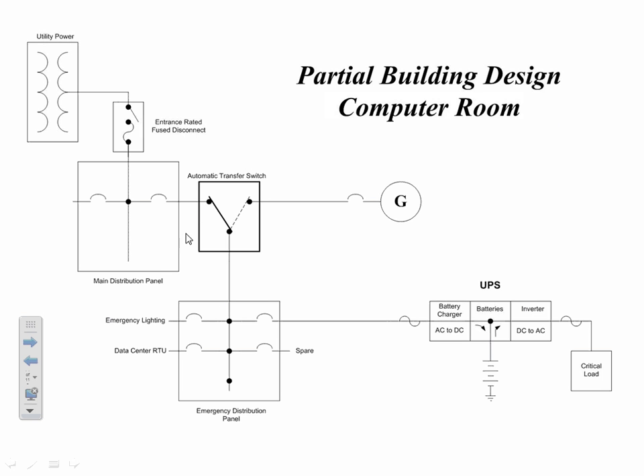We have our automatic transfer switch. We'll see that this is an open transition design. And we got our generator set here. Our transfer switch feeds our critical load. Notice that, well, critical load and other load. The very critical load is out here on the end, on the other side of our UPS system. But notice in the actual emergency distribution panel that the generator is running, also has some lighting in it. It's also got the air conditioner, the rooftop unit for the IT area, we'll say, included. And we left a spare breaker in there because we didn't trust the IT guy. He's going to put something else on there. So that's kind of the way it's set up. Again, we do have a UPS out here covering the extreme critical load in this case.